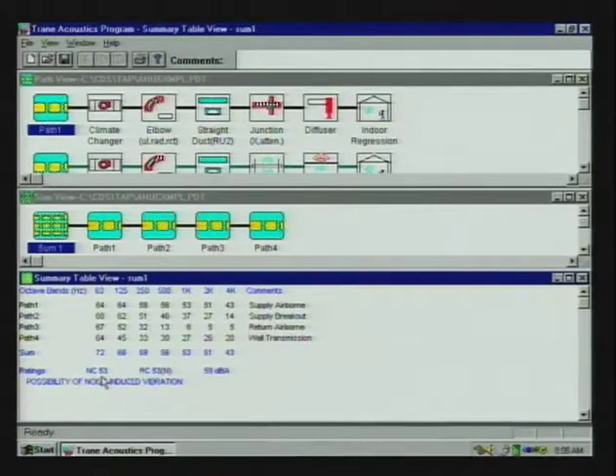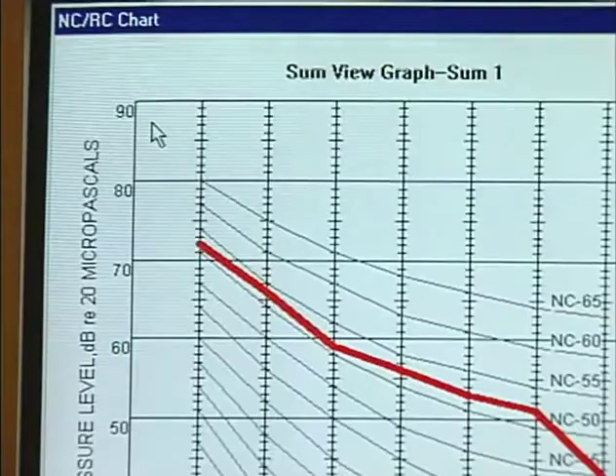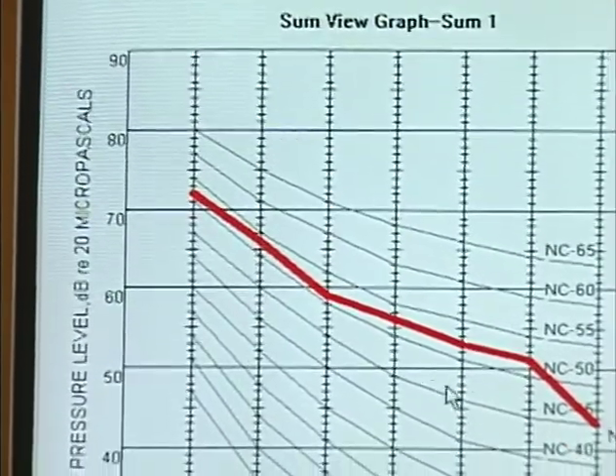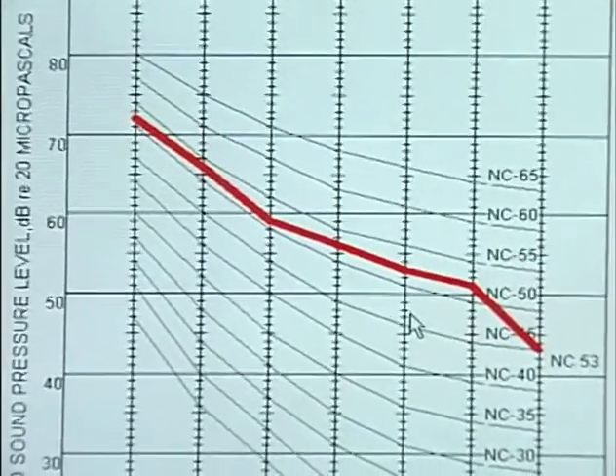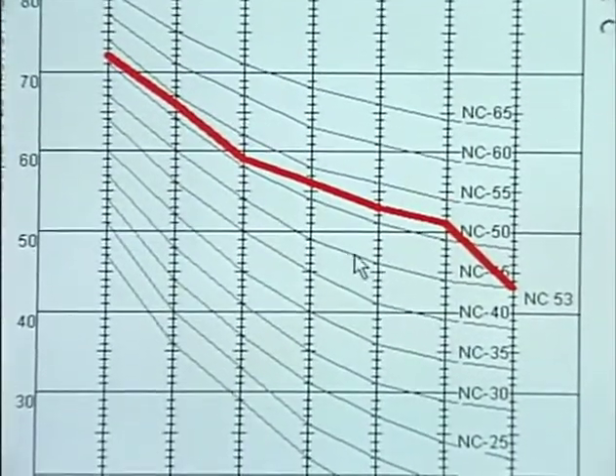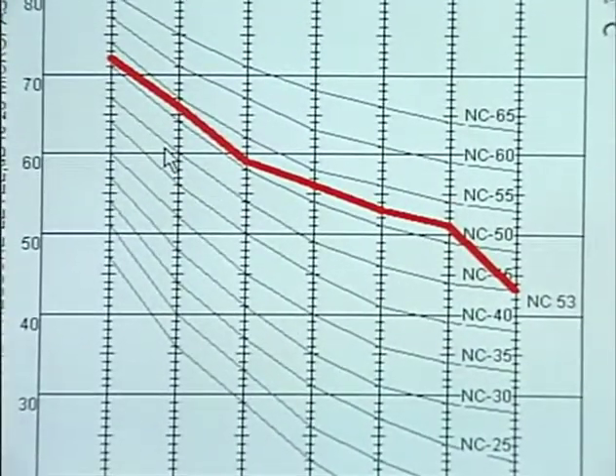At this point, what I probably would do would be to go and see how my total compares to my target. So I can plot my total on an NC chart, and let's say the target for this space was NC 45. Here's my NC 45 curve, and I can see that in every octave band except for 4K, I've exceeded my NC 45 curve, and I can see how much in each octave band.